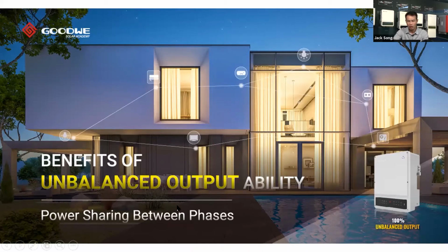This is how we realize the function, and maybe we can say how we realize unbalanced output and how we increase the benefits for the users from the unbalanced output function. With the unbalanced output function, we realize power sharing between phases inside the inverter. It's not dependent on an external device. It's all realized inside the inverter. There's no external device, like I said in the first picture. All the inverters have integrated functions, so these functions are also realized inside the inverter itself.